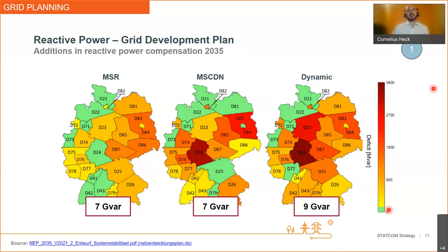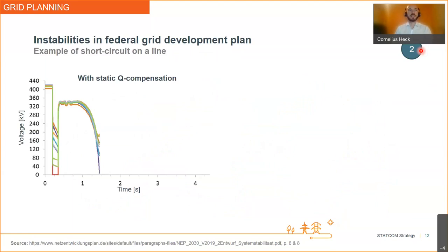But this was just to tackle the question, how much reactive power is needed. We haven't tackled the question now, how this reactive power should be comprised of. So this is done on the next slide. And what we did here is we just had our grid for the year 2035, and we put all the reactive compensation that we had in this operation scenario, and we put it all as static Q compensation. So in here, it's all MSCDN and well, a few power plants that are still left, but that's not the majority here. And as you can see, already within the first 1.5 seconds after a short circuit has occurred, we will run into a voltage collapse.